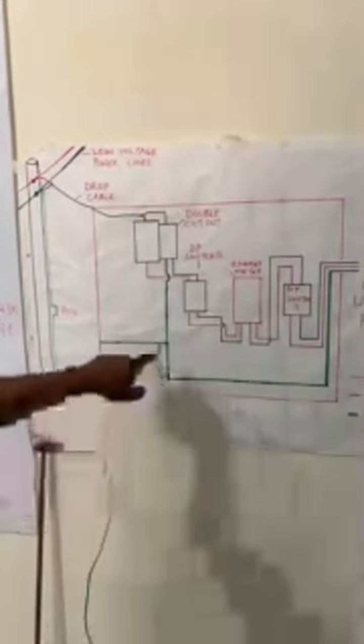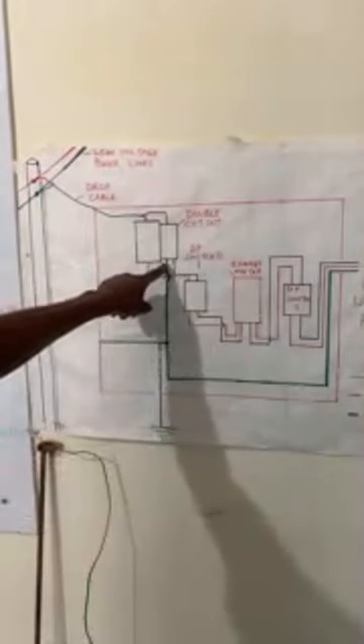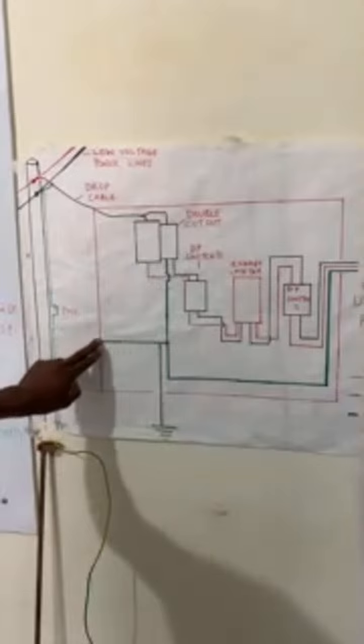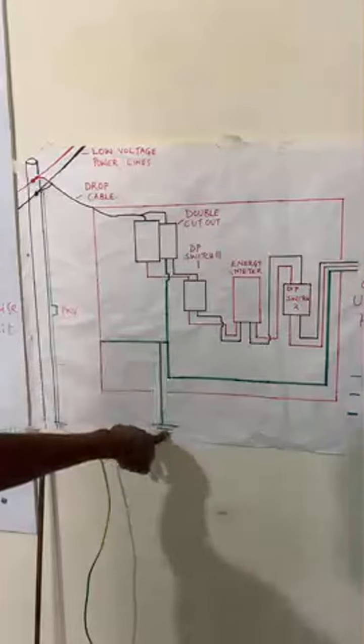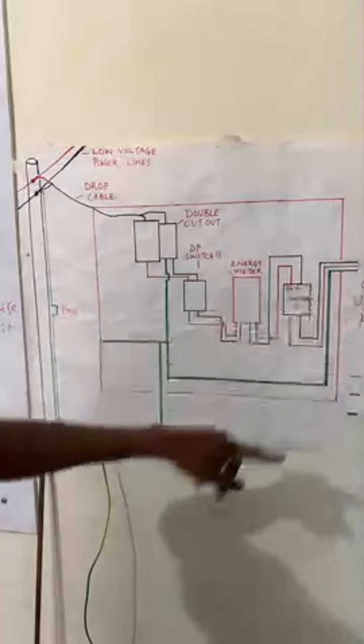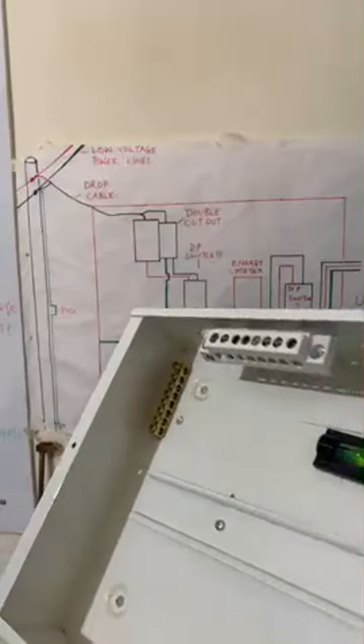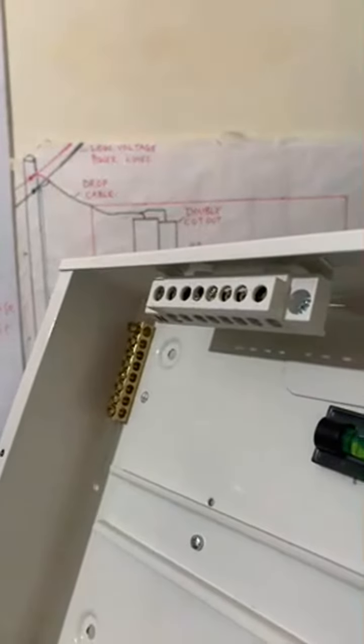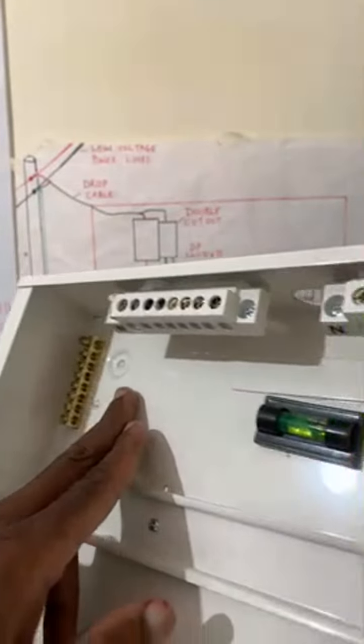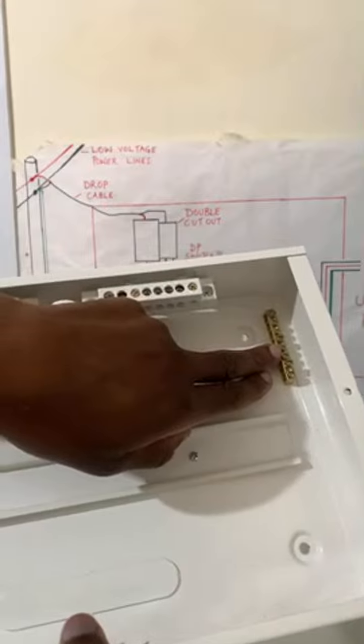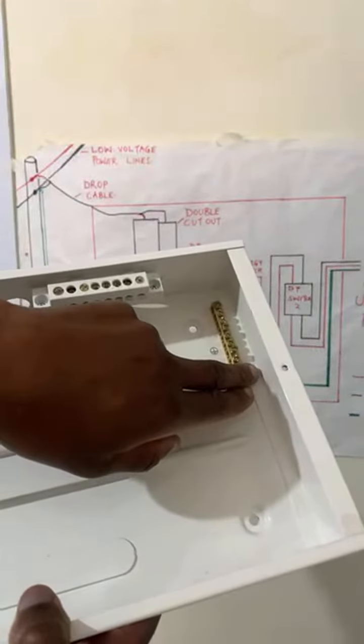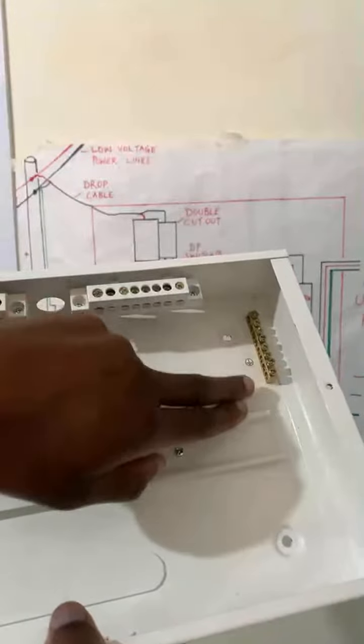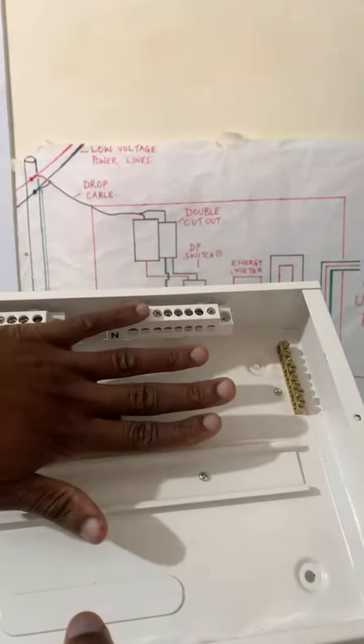If we are talking about this earth, you see this one that is coming from the neutral bonding here to the meter and then to the earth rod. And then from here, we have also connected to the consumer unit. There is nowhere else that they will be in contact with the neutral connection, my top boss. That earth connection will come all the way straight to this earth bar. And then from this earth bar, I will do a termination to this other earth bar. And then every connection that goes to the circuits, I will simply tap them here without having to tap the neutral.